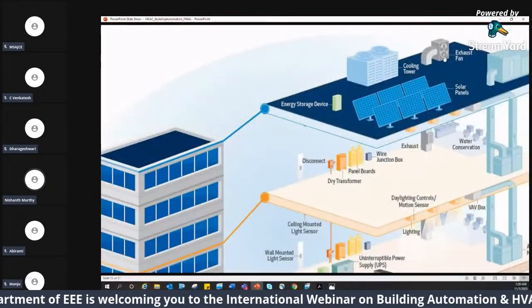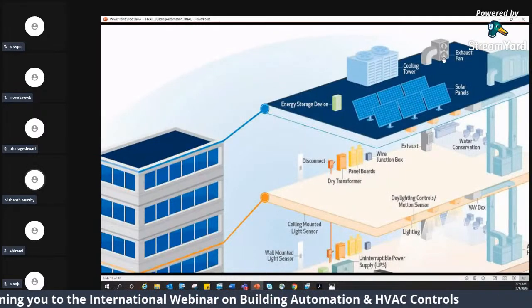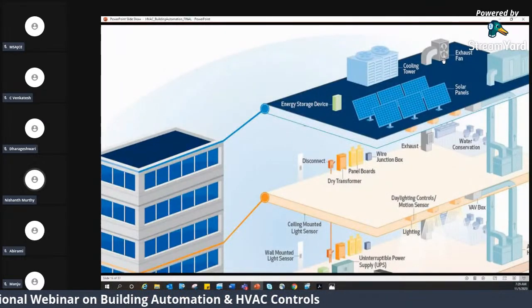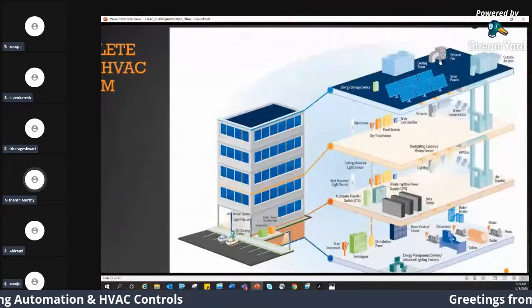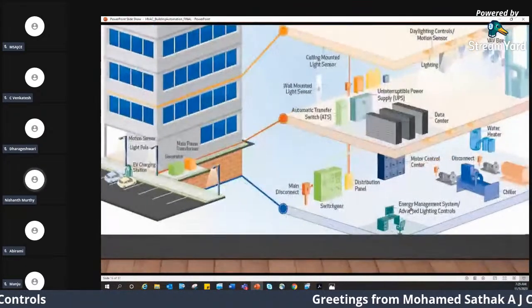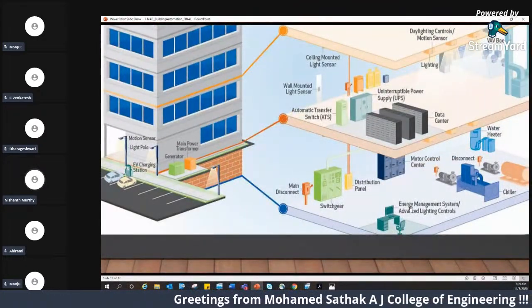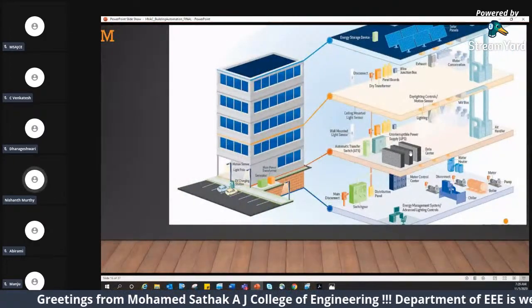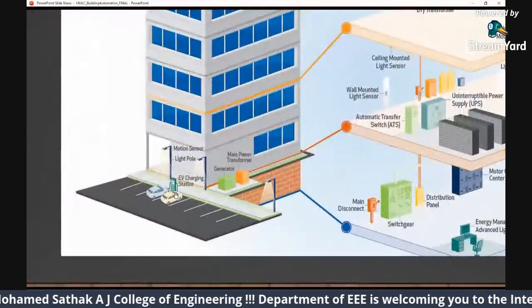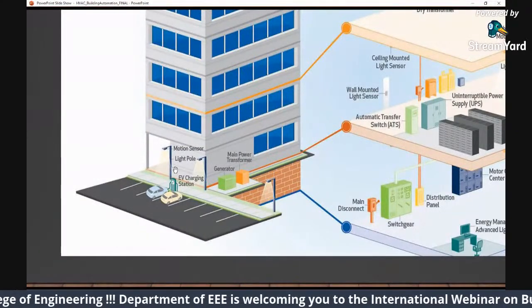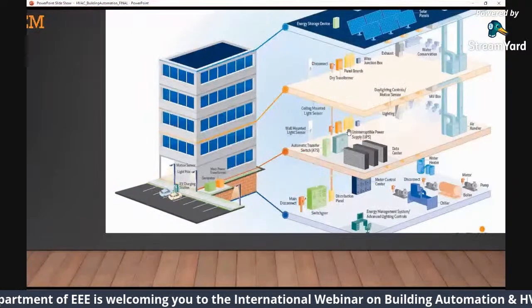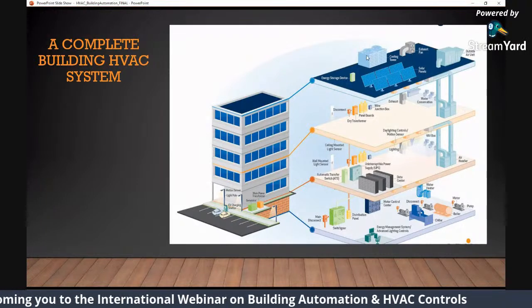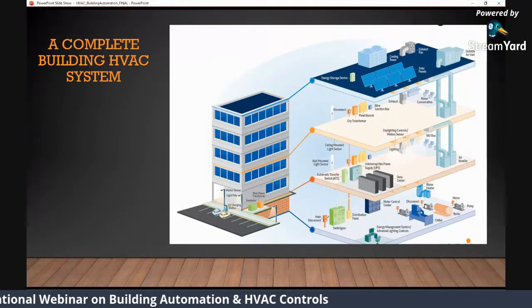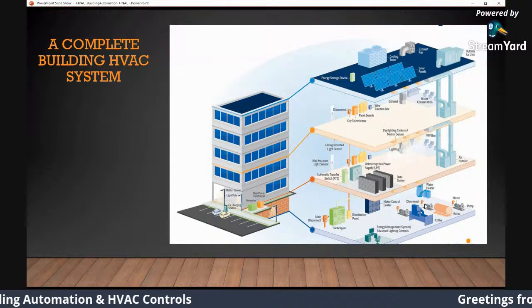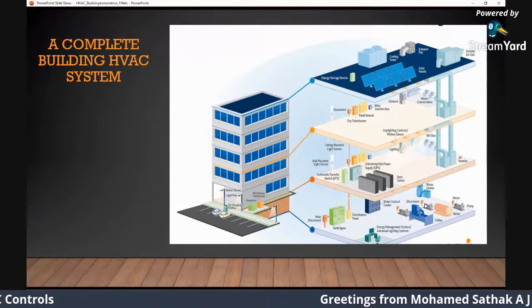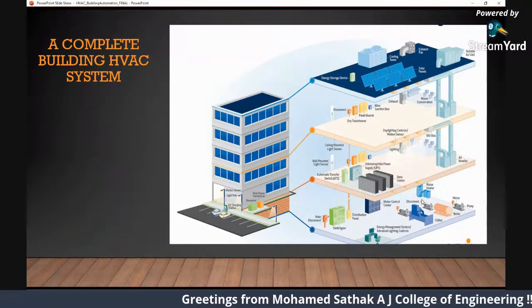But you have the exhaust fan for your kitchen, or let's say there is some hot room being served and you need an exhaust fan for your data centers or toilet systems, or we have the energy management system. This is what I was telling about, the energy recovery wheel and other components. And apart from that, we have EV charging stations, motor lights. All this comes in the building automation system, which will come in the upcoming slides. But with respect to the HVAC system, it's AHU, exhaust fan, cooling tower, chiller, boiler. All these are mechanical systems running on the basis of thermodynamic principles to keep human beings in the comfort zone. That's all I wanted to take you through from the HVAC system side.